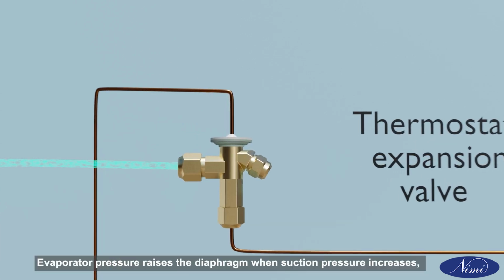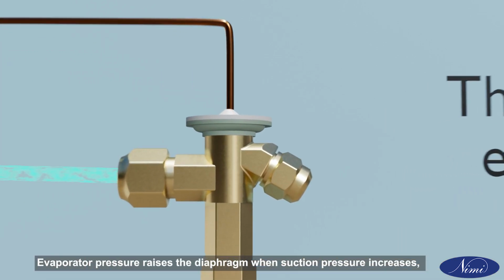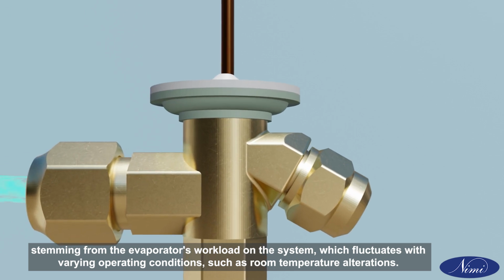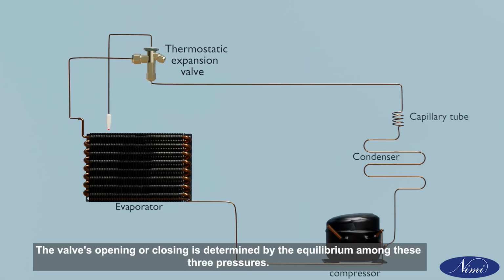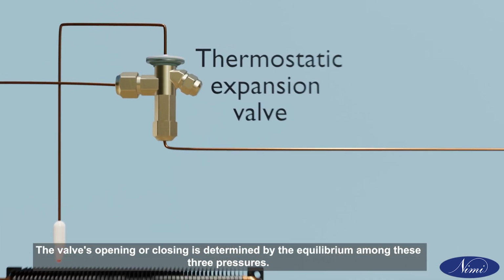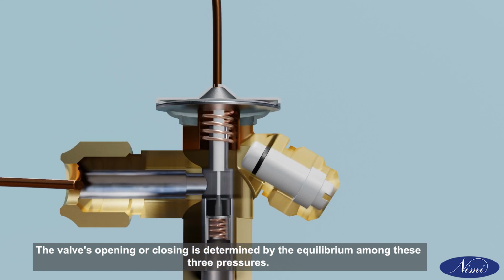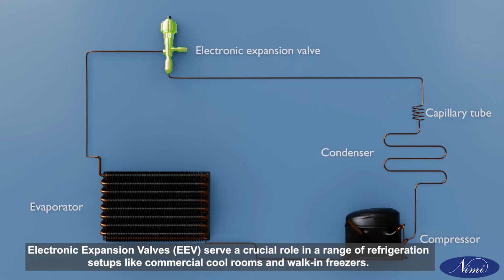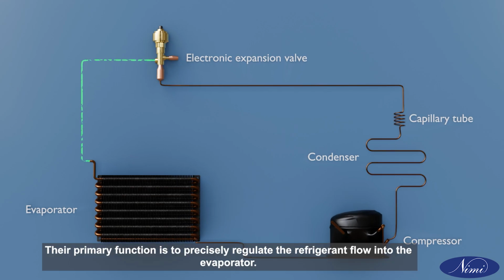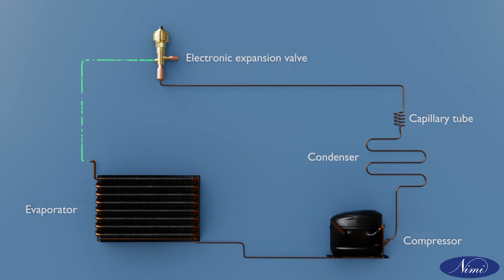Evaporator pressure raises the diaphragm when suction pressure increases, stemming from the evaporator's workload on the system, which fluctuates with varying operating conditions, such as room temperature alterations. The valve's opening or closing is determined by the equilibrium among these three pressures. Electronic expansion valves, EEV, serve a crucial role in a range of refrigeration setups like commercial cool rooms and walk-in freezers. Their primary function is to precisely regulate the refrigerant flow into the evaporator.